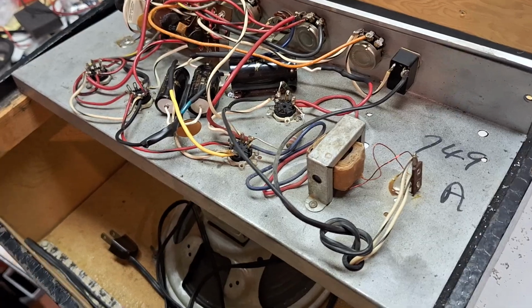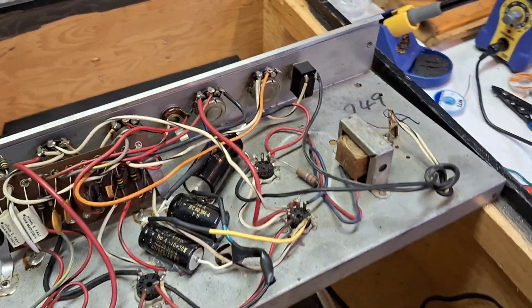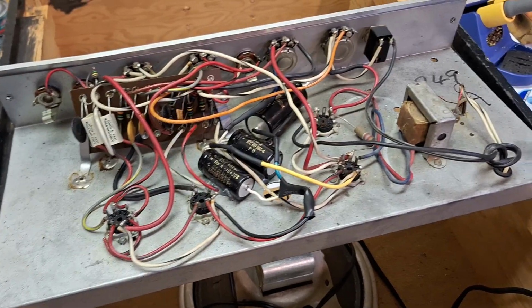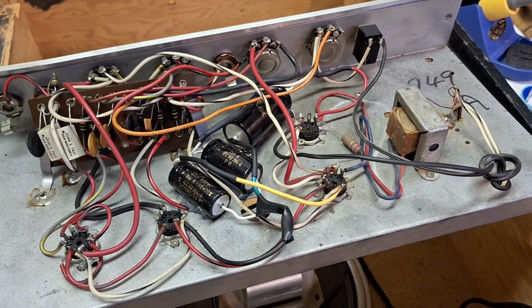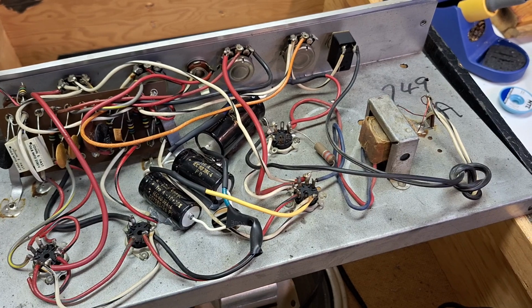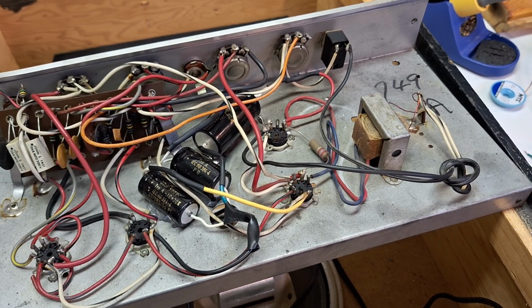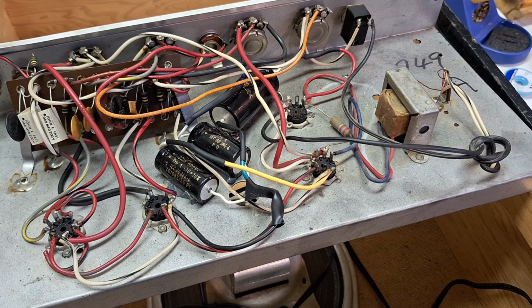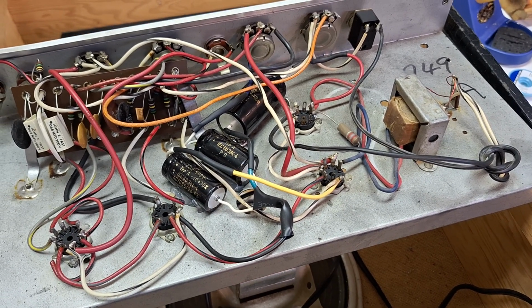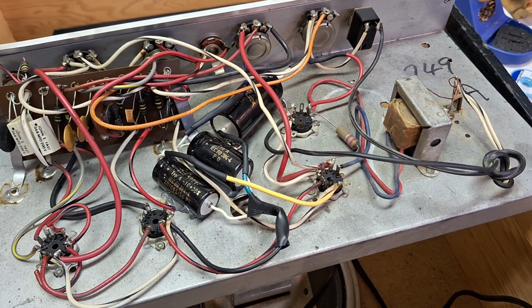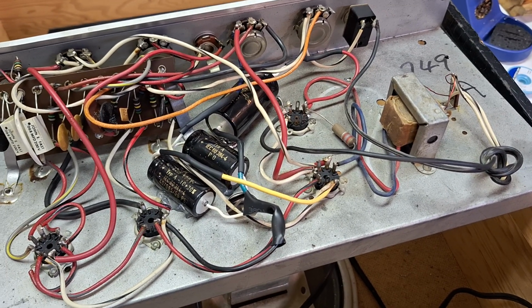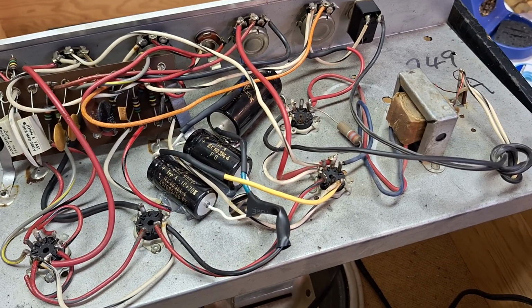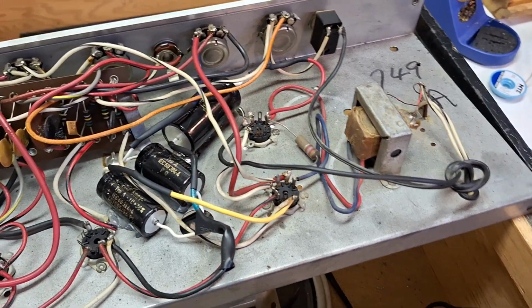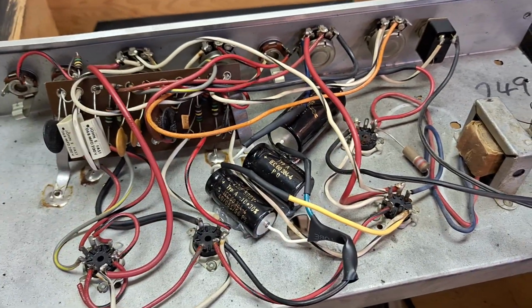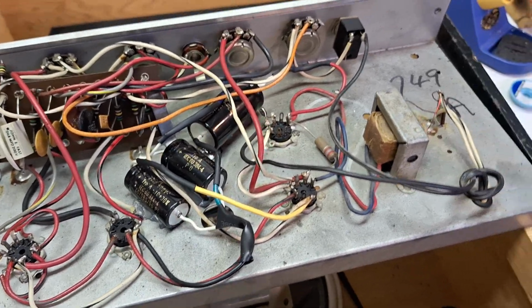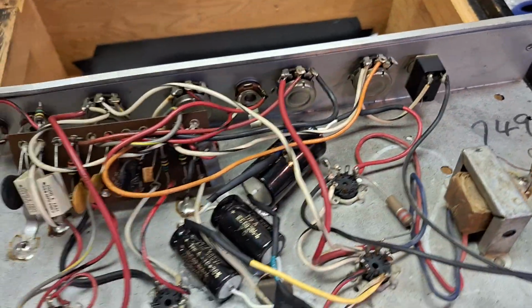But then a couple of issues arise. Now, of course, we're going to put a 3-prong cord on it and connect the earth ground to it, so that'll make it a lot safer. Just doing that. Like I said, it could be wired directly to the old power connections, but we're not going to do that because we want the amp to have all power shut off to it, transformer included, when we shut the power switch off, not just to the circuit.